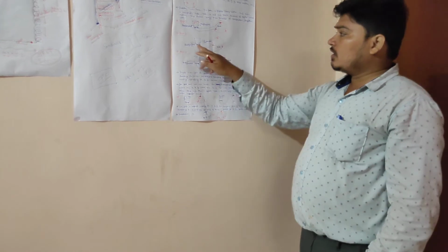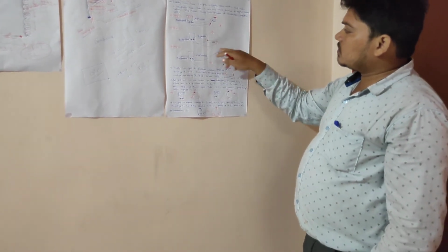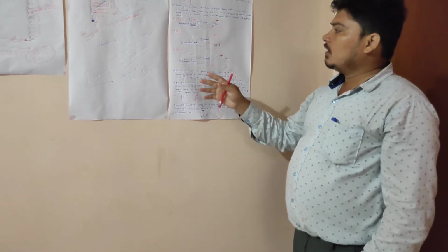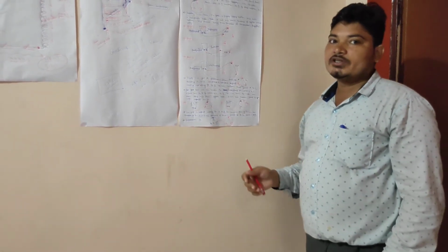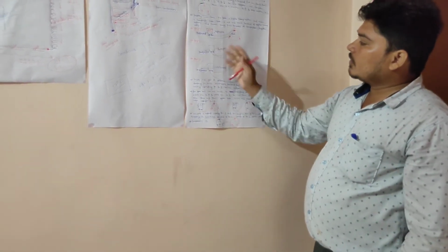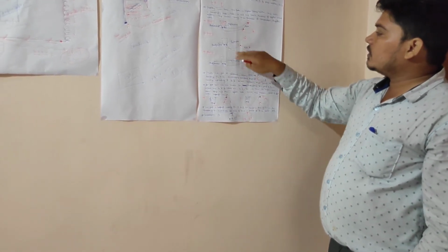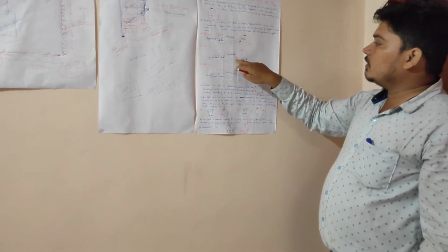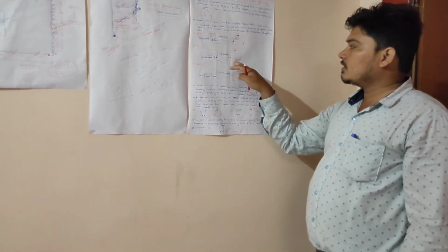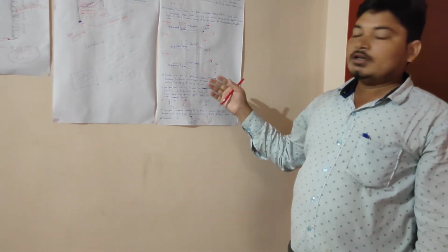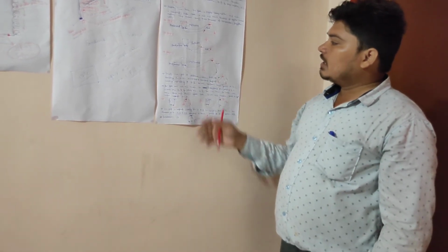Okay. In the next step, this is compressor ABC. Take the digital clamp meter and set it to continuity mode, there's no change. With the black wire and red wire, we get a reading between B and C. We get 40 ohm between B and C. That is the 40 ohm resistance value between B and C.